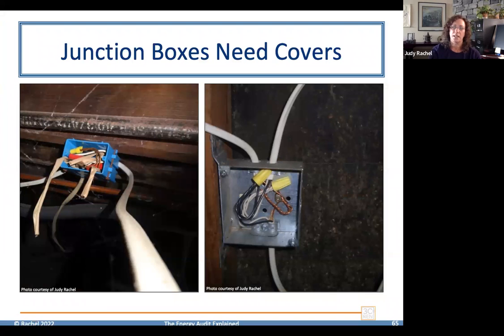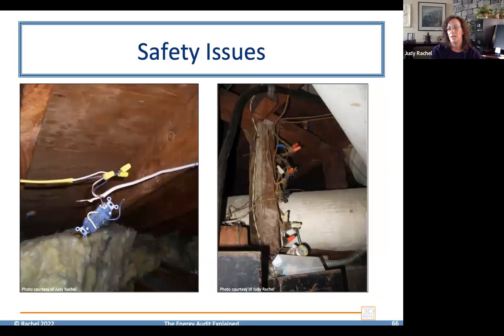Junction boxes need to be covered, and we can't be blowing in insulation or putting insulation in attics that are going to cover junction boxes that do not have covers on them. Just looking for all kinds of safety issues, and a lot of them do end up being wiring issues. Low voltage wiring needs to be able to be moved up above insulation level. There shouldn't just be loose wires that are not in junction boxes.